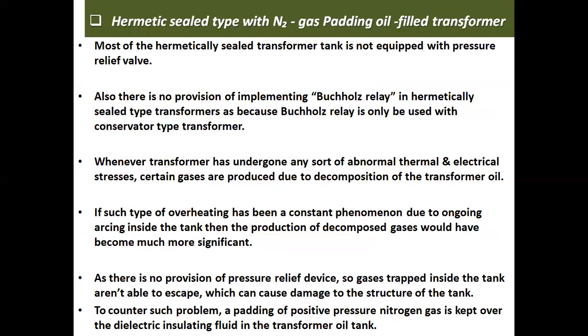Hermetically sealed type with nitrogen gas padding oil filled transformer. Most of the hermetically sealed transformer tanks are not equipped with a pressure relief valve. Also, there is no provision of implementing a Buchholz relay in hermetically sealed type transformers, because a Buchholz relay is only used with a conservator type transformer.